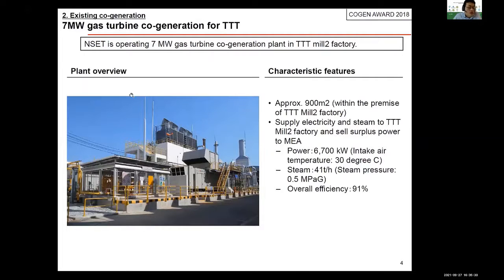This is our photo of the 7 megawatt gas turbine cogeneration for TTT. We constructed this facility in an area of 900 square meters. The capacity of power production is 6,700 kilowatt. Steam production capacity is 41 tons per hour, and its original overall plant efficiency is 91%, which is among the highest efficiency in cogeneration.